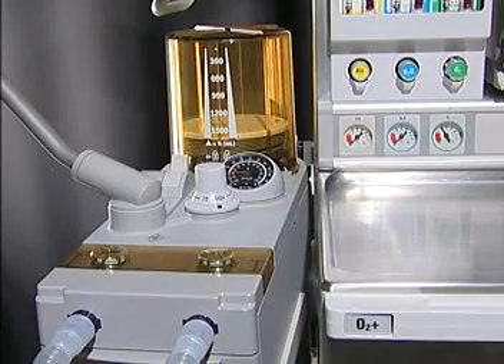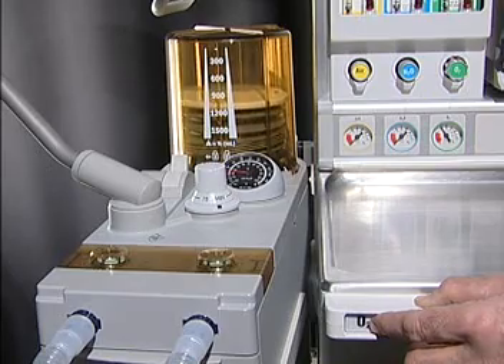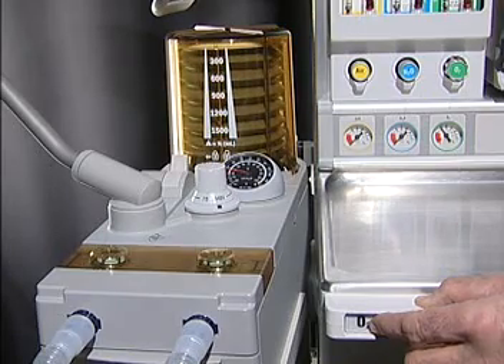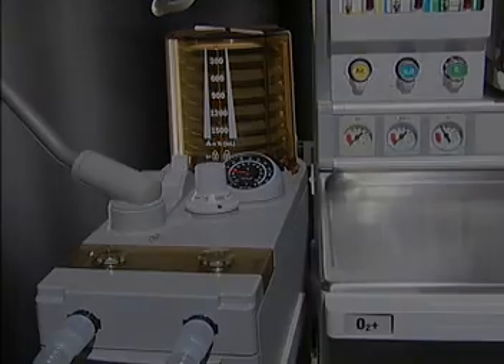When moving to the vent position, the bellows should be filled by pressing the flush valve or increasing the fresh gas flow. Failure to do so will result in an unable to drive bellows alarm and message. In the vent position, the APL is out of the circuit.